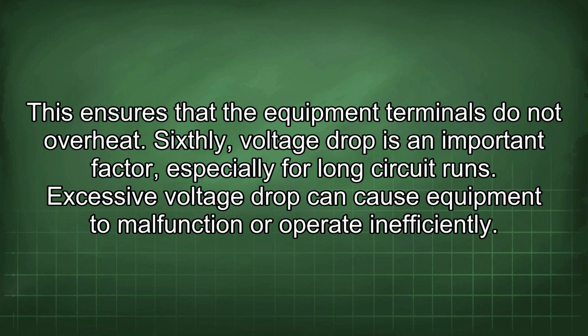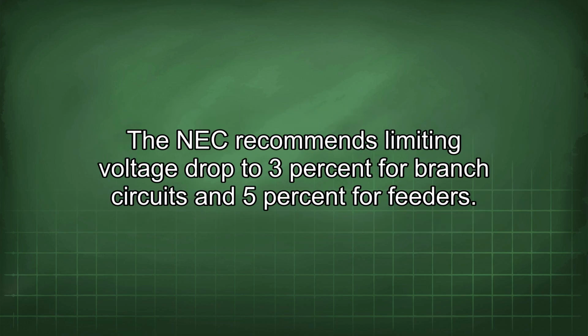Sixthly, voltage drop is an important factor, especially for long circuit runs. Excessive voltage drop can cause equipment to malfunction or operate inefficiently. The NEC recommends limiting voltage drop to 3% for branch circuits and 5% for feeders.